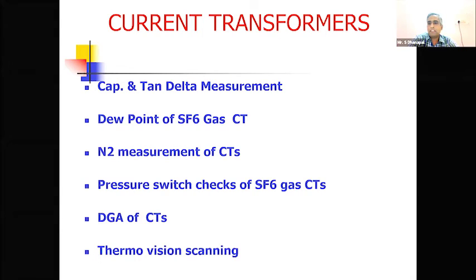Dew point measurements, we are still doing offline only. We don't have anything for continuous monitoring. Similarly, DGA and thermovision scanning - many vendors are coming up, but still in design stage, budding stage, or development stage. Full thermovision scanning cameras are normal now, but online monitoring efficiently covering the entire switchyard, where we can find hotspots and monitor everything in a controlled, total way - we are unable to do. We still follow traditional techniques over 40 years.